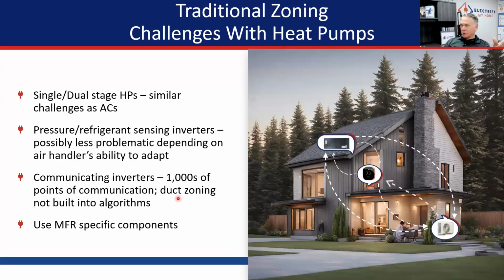Like it sees, wow, it's really hot outside. I've got some temperature coming back in my return air, but my coil, my supply temperature is really low. It throws the whole thing out of whack, and that can cause mystery fault codes and things like that.